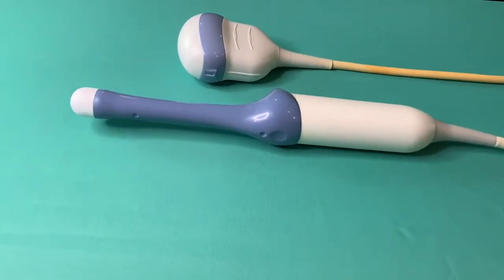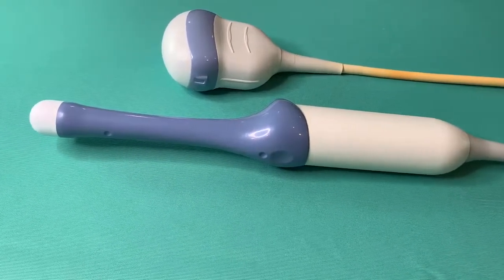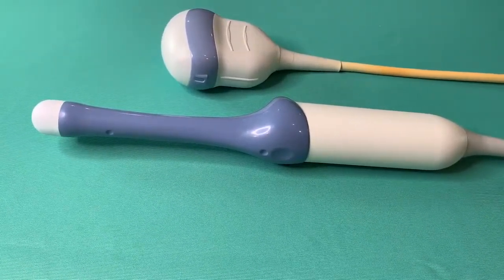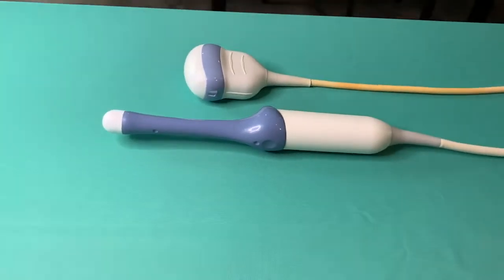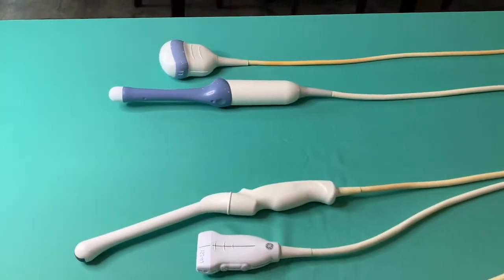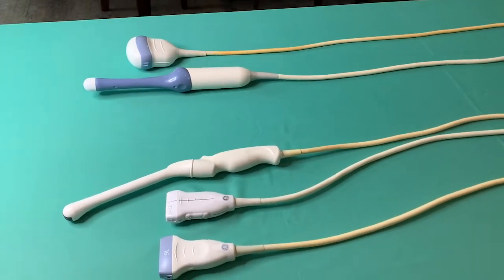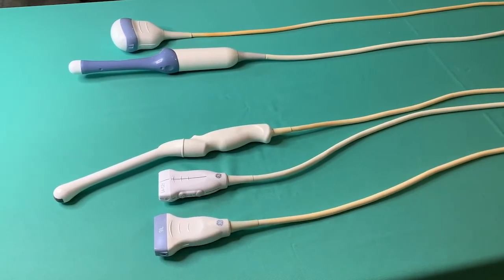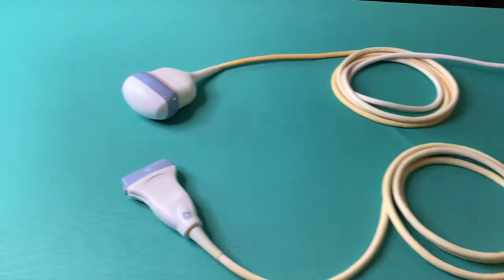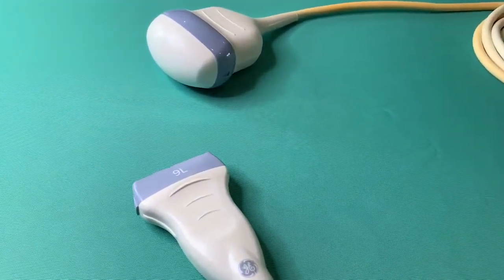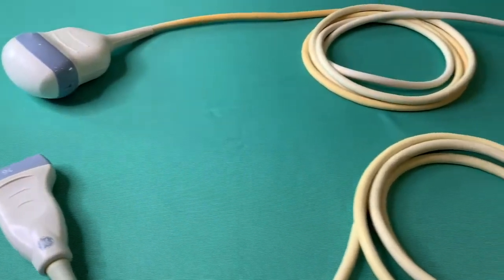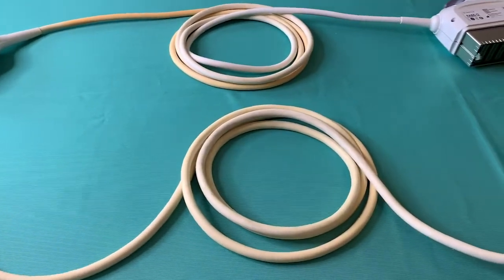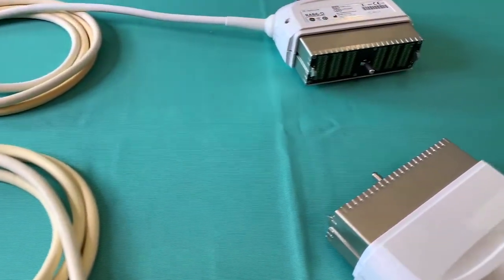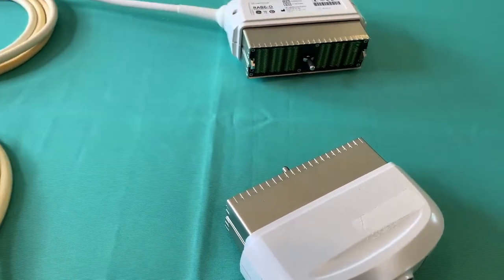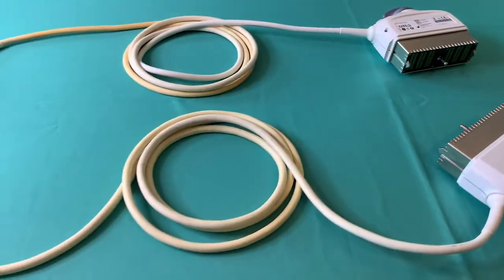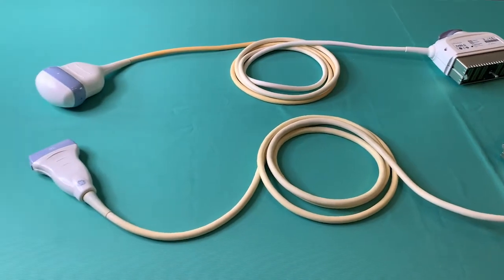3D probes can be further segmented into mechanical or matrix based upon technical complexity of the design. Matrix probes have a physical design similar to that of standard probes, so our focus here will be limited to mechanical 3D probes. Begin the visual inspection at the probe's scan head and work your way along the probe, ending at the system connector. Starting at one end and ending at the other will prevent potentially skipping important areas of the probe. Don't assume that anyone at the facility is performing visual inspections or inspections as detailed as covered here.